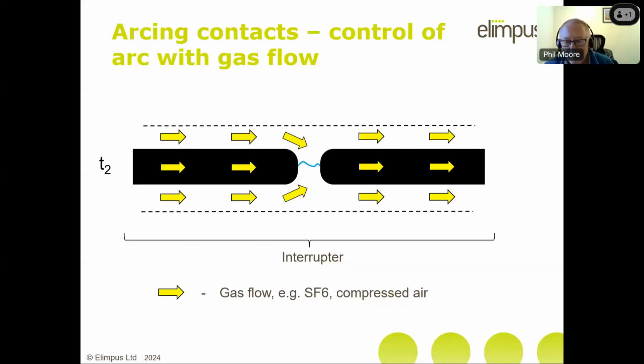If you were dealing with the earlier generation of circuit breakers, the air blast circuit breakers, the gas would be compressed air, but it's the same principle. You might think that if you were to continue moving the contacts apart and continually cooling it down with a supersonic flow of sulfur hexafluoride gas, eventually the arc would go out. And the true reality is it probably won't, because once you've started an arc, it's very difficult to get rid of it.